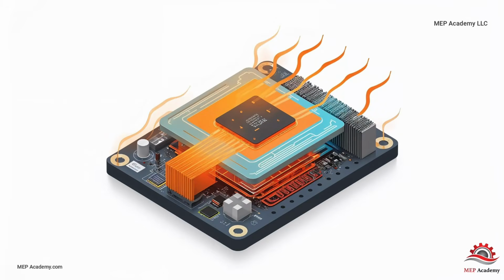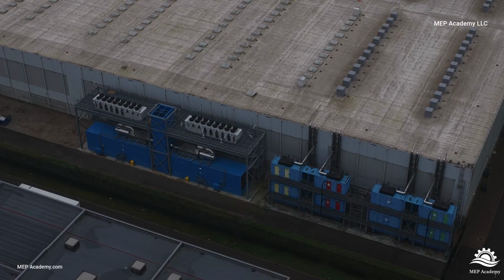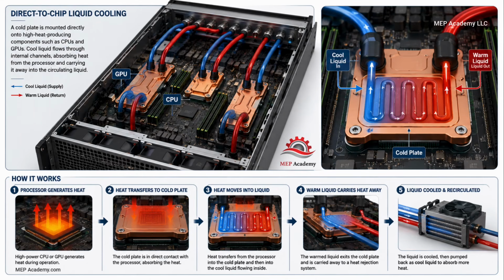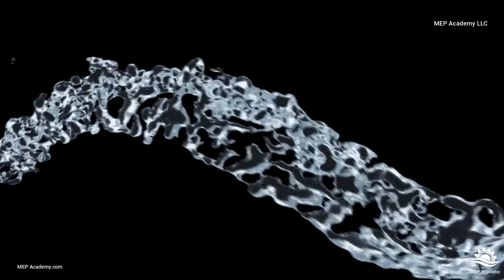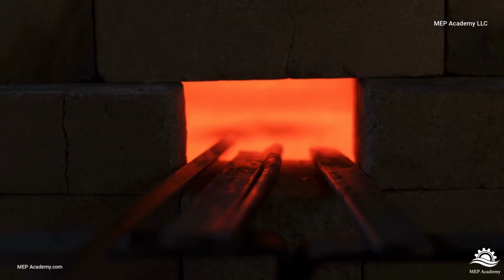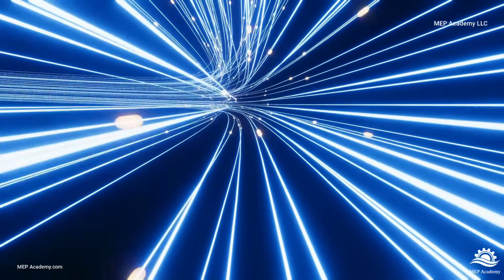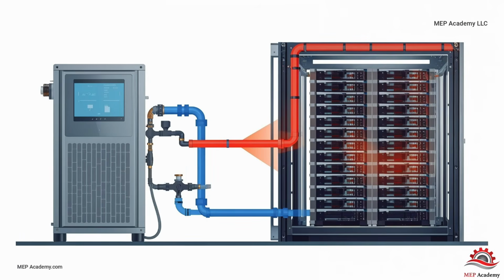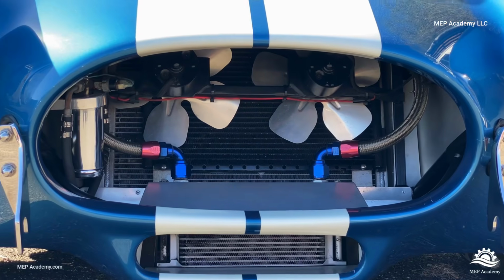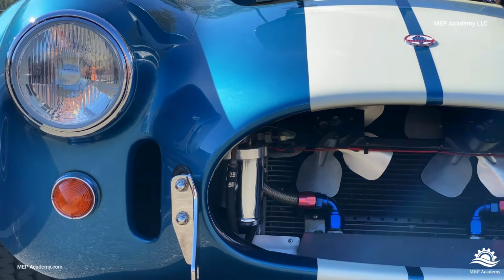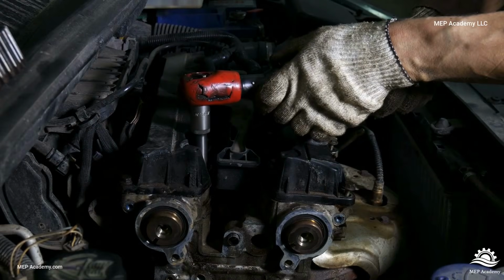Direct-to-chip cooling is currently the most common liquid cooling technology being deployed in AI facilities. In this approach, a cooling device called a cold plate is mounted directly onto high heat-producing components such as CPUs and GPUs. The cold plate contains small internal channels. Cool liquid flows through these channels. As the processor generates heat, that heat transfers into the cold plate and then into the circulating liquid. The liquid carries the heat away from the server. The warmed liquid leaves the rack and returns to a cooling distribution system where the heat is removed before being sent back again. It's very similar to the cooling system inside an automobile engine. Heat is collected from the engine and carried away by a circulating fluid.